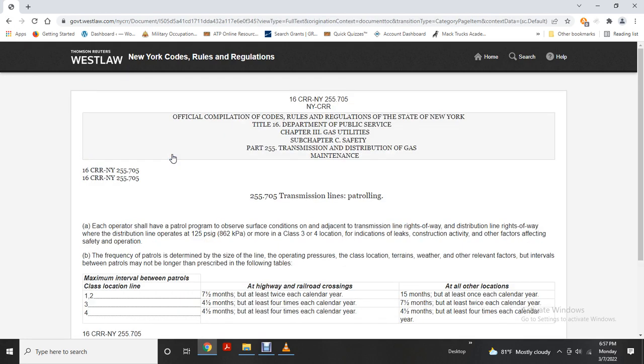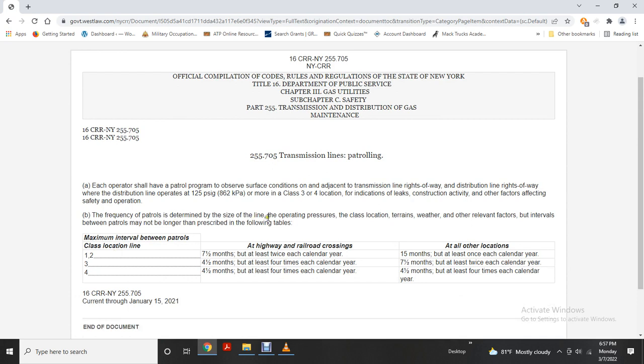Transmission lines and patrolling. Each operator shall have a patrol program to observe the surface conditions on and adjacent to the transmission line right-of-way, for distribution lines operating at 125 psi or more in class 3 or 4 locations. Patrols indicate leaks, corrosive action, and other factors affecting safe operation. Frequencies are determined by the size of the line, the operating pressure, the class location, terrain, weather, and other relevant factors.